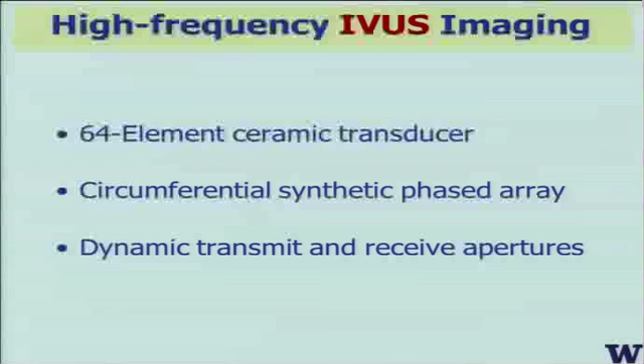This was the state of the art circa 20 years ago: a single element transducer, mechanically rotated and delivered over a guide wire into a coronary artery. Typical dimensions here, this is a 3 French or so device, so it's a millimeter-scale device. So this was replaced with this, which is these 64 elements now delivered over the guide wire. It went right through the middle like a donut, so there were no image artifacts. And all the electronics driving that were integrated into the front end.